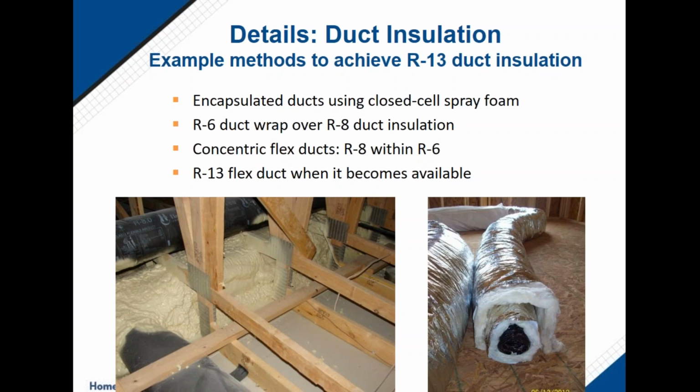So the way I look at this is, if you do something like this, you do need to seal both of those vapor barriers. You install the inner liner first, and this would apply to duct wrap as well. You've got to seal that, and then you pull the other outer jacket over it, and you've got to seal that as well. So I think you're sealing both. I think duct sealing is critical for any duct system in an attic, whether it's buried or not. And this is almost another layer of protection. If for some reason moisture were to get through a tear, for example, in the outer jacket, you'd still have the inner jacket that would provide protection against condensation.